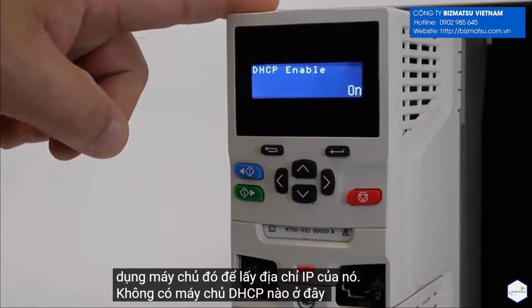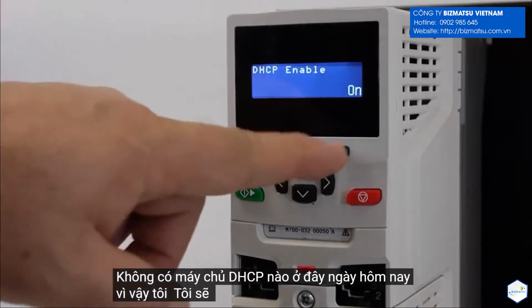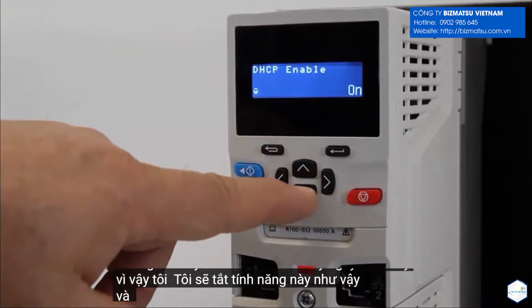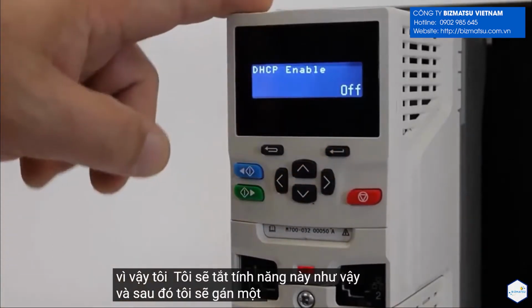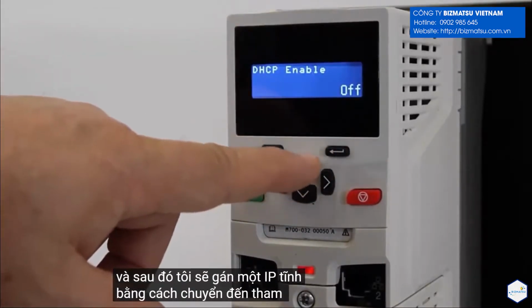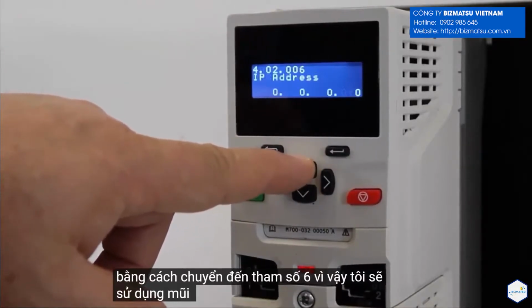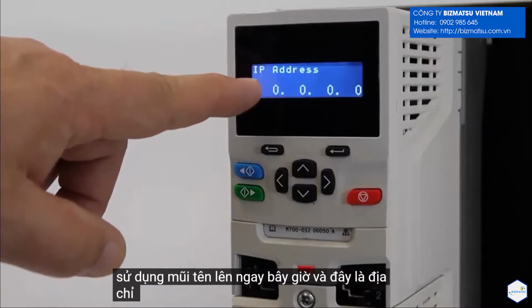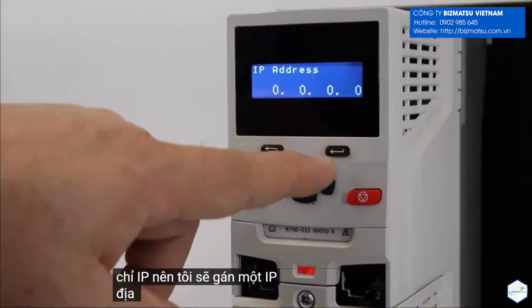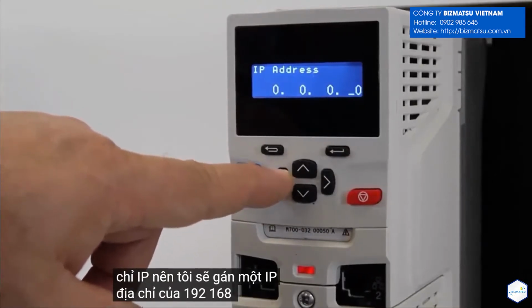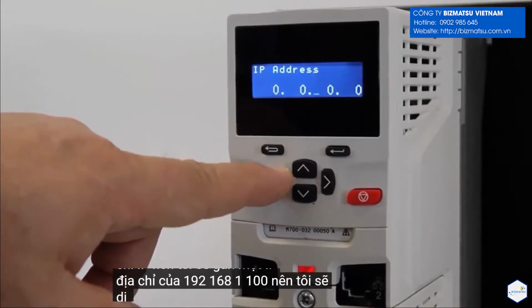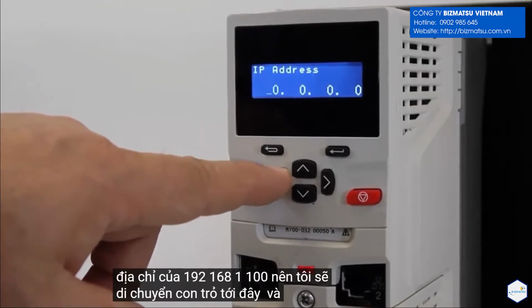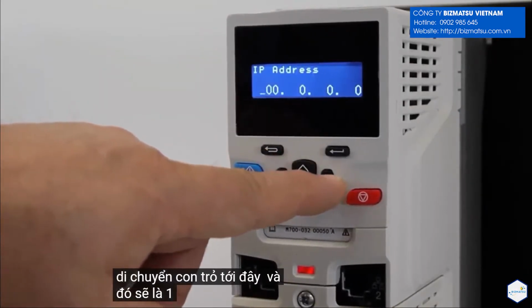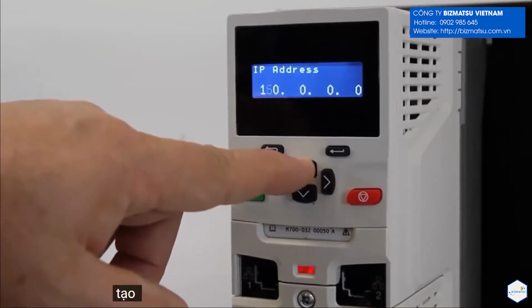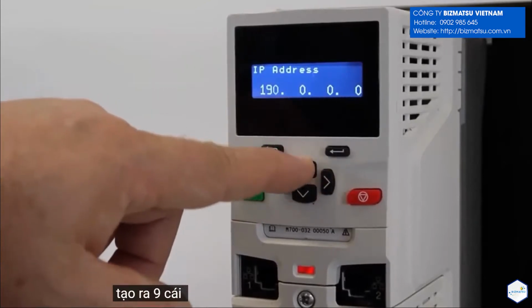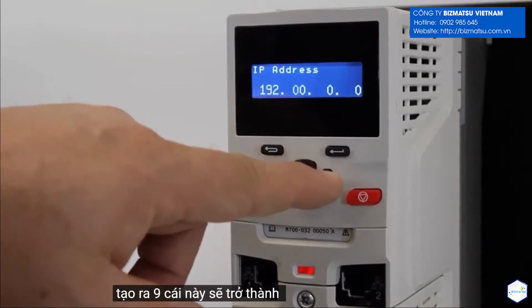Well, there is no DHCP server here today, so I'm going to turn this off, like so. And then I'm going to assign a static IP by going to parameter 6. So I'm going to use the up arrow now, and here's the IP address. So I'm going to assign an IP address of 192.168.1.100. So I'm going to move my cursor all the way over here. And that's going to be a 1. Make that a 9. This is going to become 168.